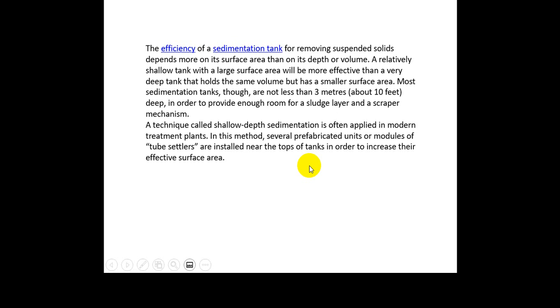Large, heavy particles settle out readily, but smaller and lighter particles settle very slowly or in some cases do not settle at all. Because of this, the sedimentation step is usually preceded by a chemical process known as coagulation. Chemical coagulants are added to the water to bring non-settling particles together into larger, heavier masses of solids called floc. Aluminum sulfate, alum, is the most common coagulant used for water purification. Other chemicals such as ferric sulfate or sodium aluminate may also be used.